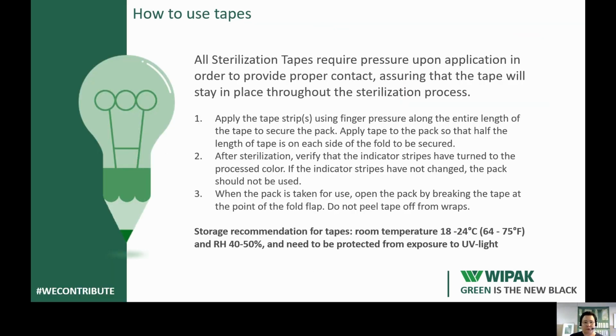Then some words about how to use the tapes. It's important to remember that all the sterilization tapes are pressure sensitive. They require pressure when they are applied to the wrapping material so that the tape really stays and does not lift during the sterilization process. Therefore, when applying the tape strip to the wrapped pack, finger pressure needs to be applied along the whole length of the tape so that it really sticks to the material and stays there while the pack is processed in the sterilization process.